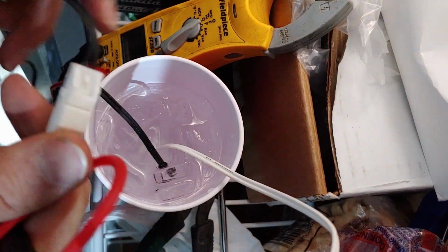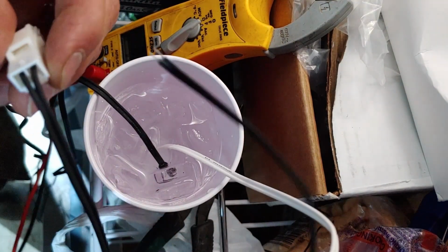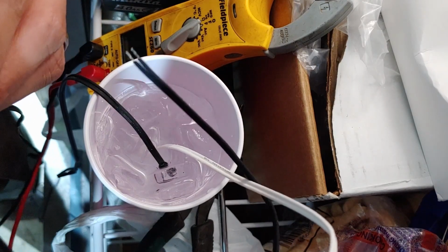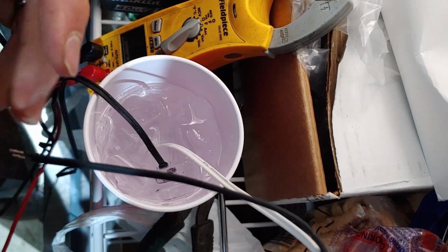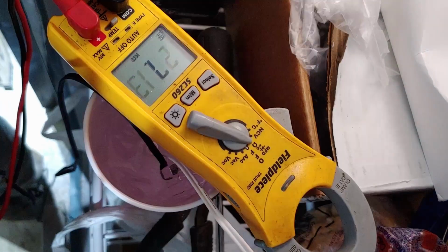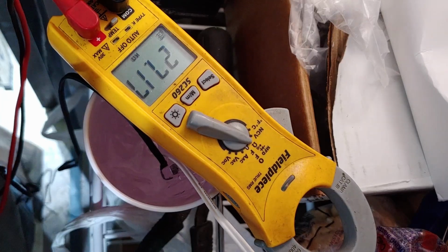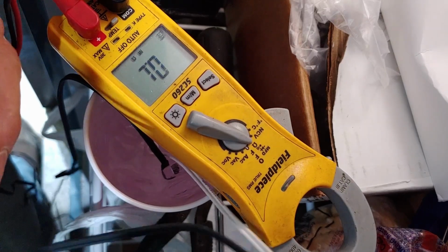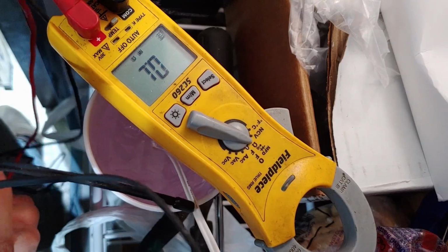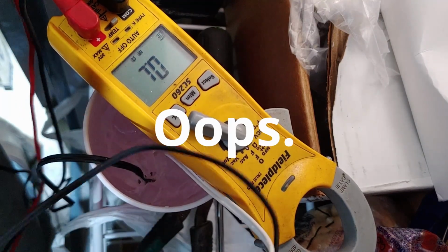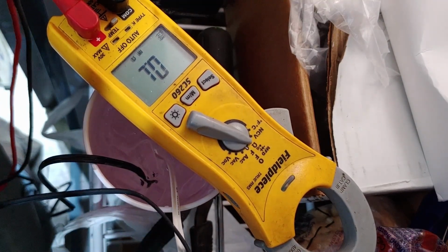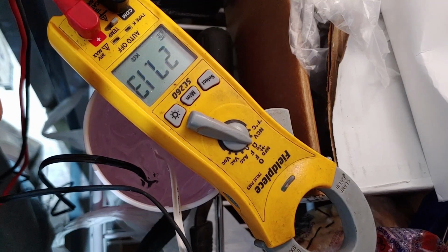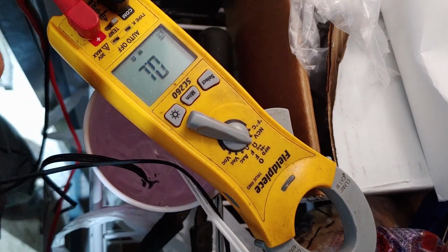Here's that new one. So where I'm checking it is just in the back of the probe, and you'll want it to be unplugged from the control like I have it right now, like this. You can see we're getting 27, so technically a little bit out of tolerance, or maybe we don't have this probe just deep enough in the ice. But big difference between the old one and the new one. So that's how you test these probes.